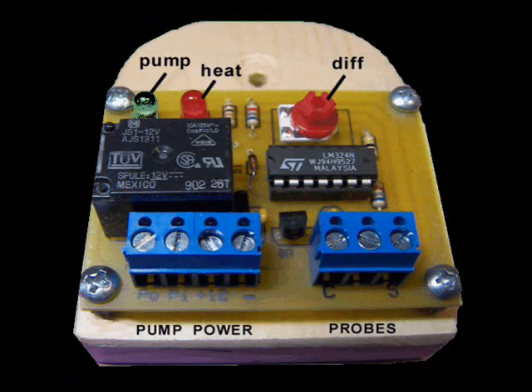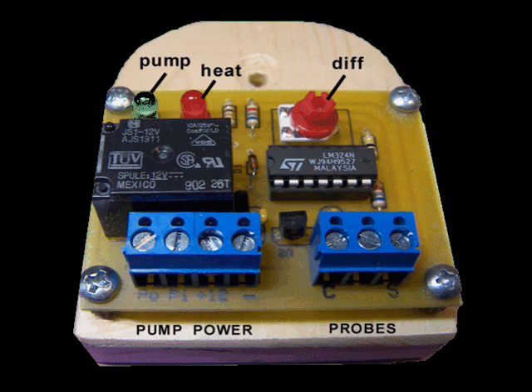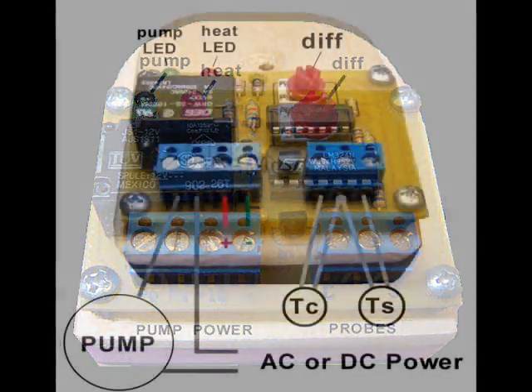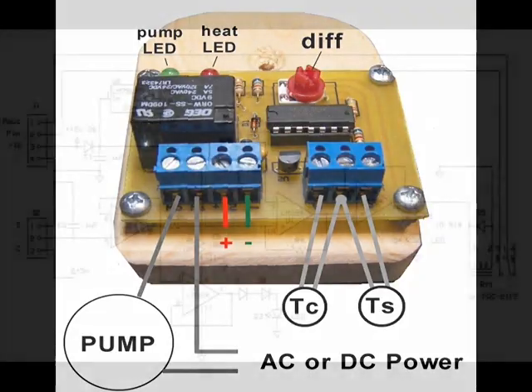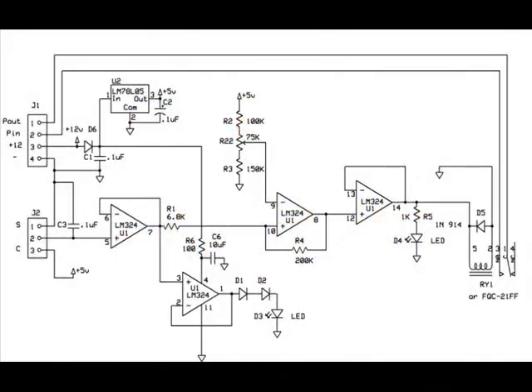As you know, differential controllers respond to differences in pressure, temperature, or other physical conditions. Differential thermal controllers respond to temperature. They activate pumps when collector temperature is greater than storage temperature.